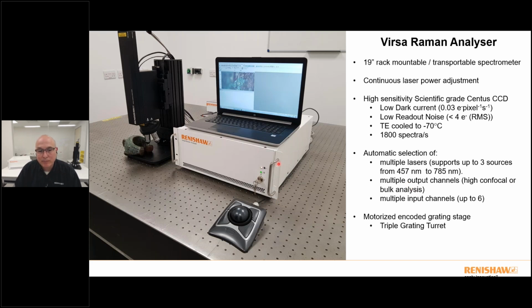The box itself can support 2 lasers, and then we have an option for a separate box, which introduces a 3rd laser source as well. And then we can take those lasers and launch them into multiple fiber probes, and we can accept multiple return fibers from those remote analysis points as well. And then lastly, there's a triple grating turret using a Renishaw encoded grating stage. So we have the ability to vary the spectral resolution based off of whatever laser sources we're changing there.